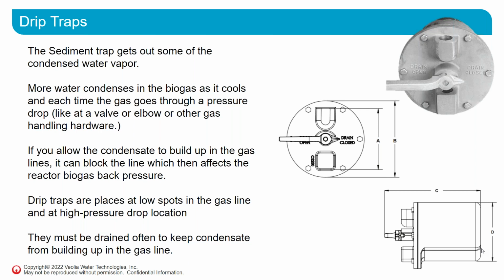And that gives you an opportunity to remove that condensate from the line without having to isolate the line, because they're designed in a way that when you open the drain, it blocks off the biogas. So you don't have biogas leaks, again for both safety and performance. They should be drained fairly often. You should follow the manufacturer's recommendation and also adjust according to your plant situation. Usually I recommend emptying them at least once a shift, and then you can track how full they get. The more gas you produce or the colder the temperature at your plant, the more frequently you should drain it.